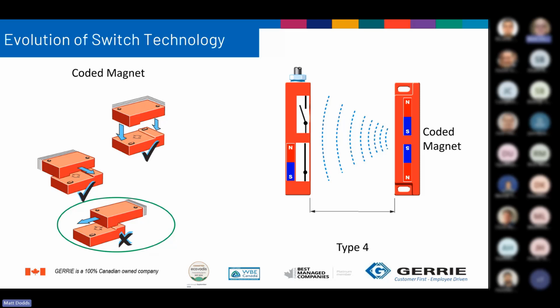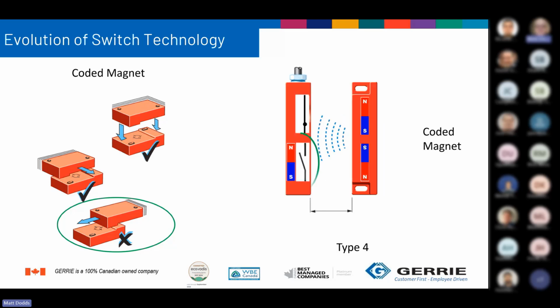So if we look at the illustration on the right, note there is a magnet inside the sensor that holds the normally open contacts closed. When the actuator is within the operating range, the magnetic field of the actuator cancels out the magnetic field in the sensor and the contacts open. And I apologize if the polarity of the magnet inside the actuator is incorrect. It's been a while since I've looked inside one of these.